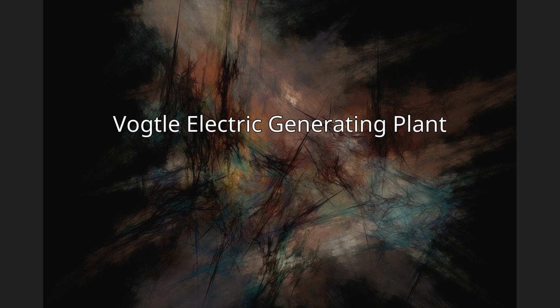Each unit has a Westinghouse pressurized water reactor (PWR) with a General Electric steam turbine and electric generator. Units 1 and 2 were completed in 1987 and 1989, respectively. Each unit has a gross electricity generation capacity of 1215 MW, for a combined capacity of 2430 MW. The twin natural draft cooling towers are 548 ft (167 m) tall and provide cooling to the plant's main condensers.